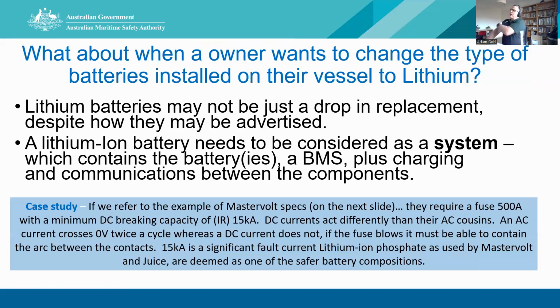A lot of people think that you can just drop in a new battery and change it over, but as you've seen, you're increasing the risk, and the potential of hazard is higher with a lithium battery compared to a lead acid. Lithium batteries may not be just a drop-in replacement, despite how they may be advertised. A lithium-ion battery needs to be considered as a system, so it contains the battery or batteries, the BMS, plus the charging and comms between these components.